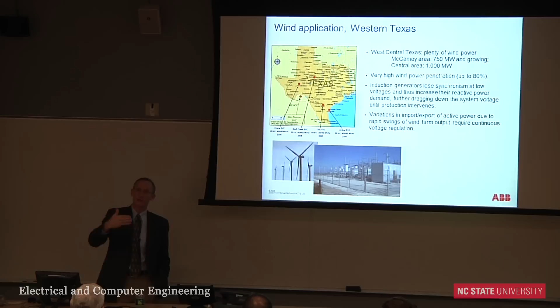But the real constraint on transmission lines has to do with the stability of the grid. The grid operates based on what's typically an N-1 or N-2 contingency, meaning it has to remain stable if any part of the infrastructure trips off or is otherwise compromised. If you have too much power going down one transmission line and lose that line, you can lose stability. That's the main limitation, and a static VAR compensator relaxes that constraint by providing voltage support, allowing you to transfer more power down the grid.